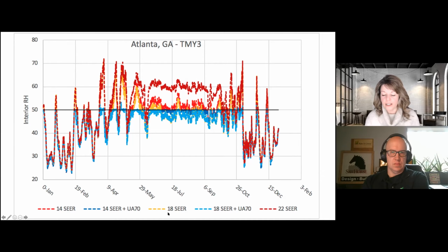And then we did the same with 18 SEER, which is the yellow, 18 SEER with a dehumidifier. And then this one's interesting because I hear it all the time: well, I've got multi-stage equipment, or I've got variable speed, so my equipment is better at controlling relative humidity. And the reality is still 2/3 of the BTUs of that equipment is focused on sensible, and 1/3 is on the latent. So you're not changing the engineering of that equipment by adding variable.